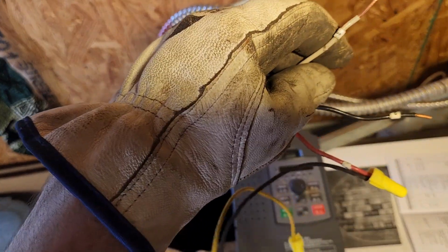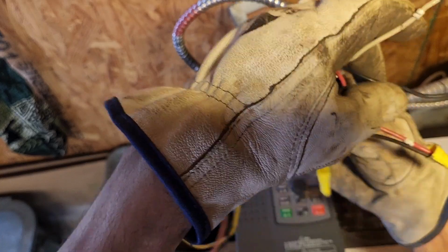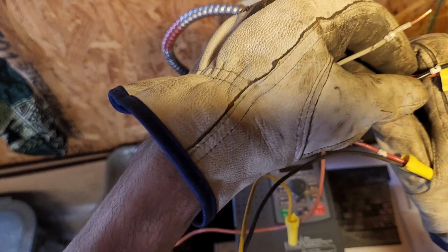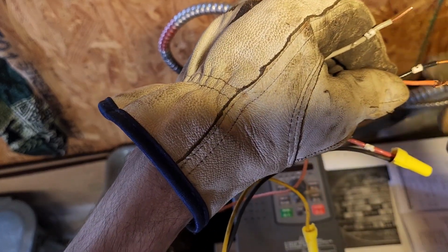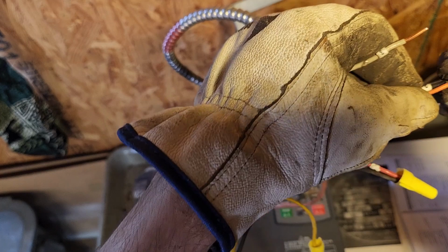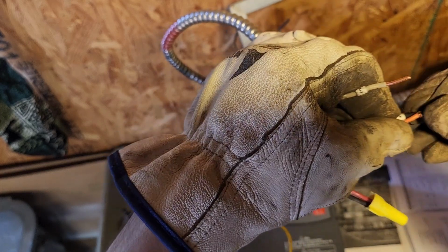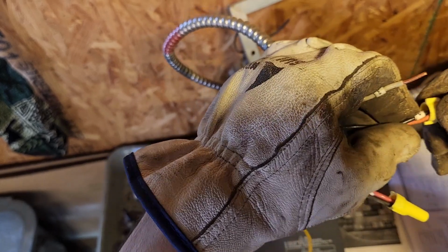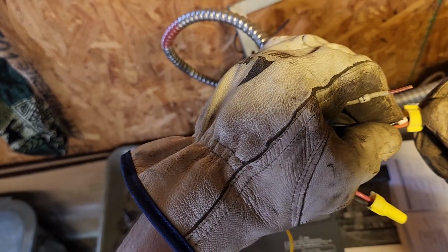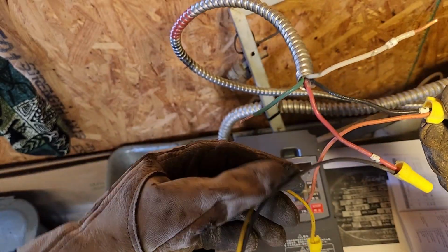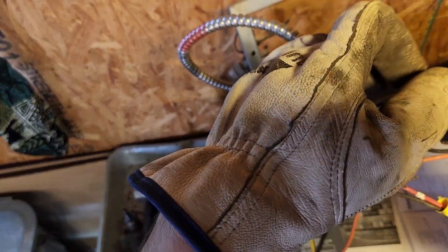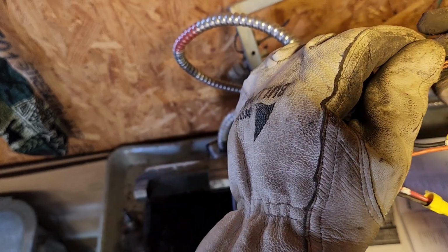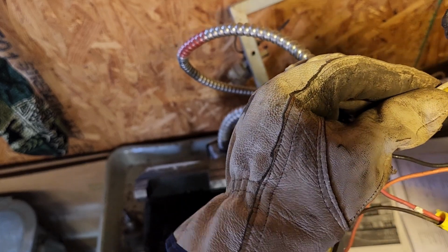It also helps if you always hook up your 3 phases the same colors, in the same order, as a standard. So you know that if you see one that's wired, and instead of brown, orange, yellow it's orange, brown, yellow, that's probably a motor that was running backwards. So you swap 2 phases around to make the motor run the other direction. I don't know if I'll have to do that or not. You can reverse directions with a VFD.